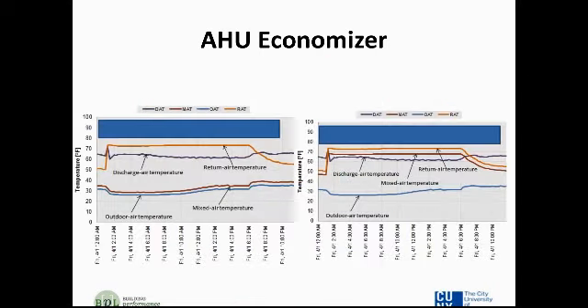The fans, it doesn't show that they're on here, but obviously they are, because the cooling coil valve signal shows that it's absolutely closed. It rides the x-axis, if you will, or the time axis, way down at the bottom at 0. So here we're actually economizing fully, and there's no need for cooling coil valves to be open, and therefore we're not using the energy that gets sucked up by the chiller. So some real energy savings here.